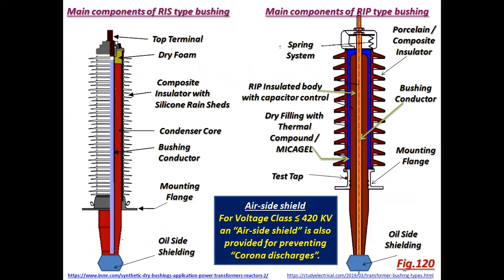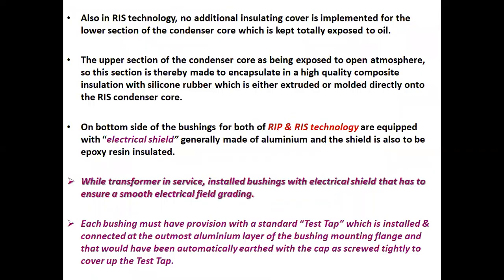See the diagram of main components of RIS type bushing as well as RIP type bushings. Air side shield for voltage class 420 kV and below, and the air side shield is also provided for preventing corona discharges. Most important, in RIS technology, no additional insulating cover is implemented for the lower section of the condenser core, which is kept totally exposed to oil.